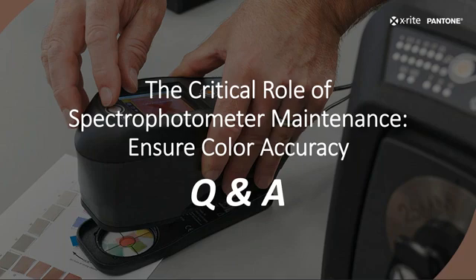Yes, there are, and there is guidance about that in the tiles themselves. But I can tell you right off the top of my head that the way that we clean them, you need a soft, lint-free cloth, and you typically want to use water or isopropyl alcohol, and that's it. Nothing more stringent than that. And with Net Profiler tiles, as with your calibration tile, same kind of cleaning is done. You want to clean them, and then you need to let them air dry for a good amount of time, like 30 minutes, because it might look like that water or isopropyl alcohol evaporated very quickly, but it still leaves a bit of residue.